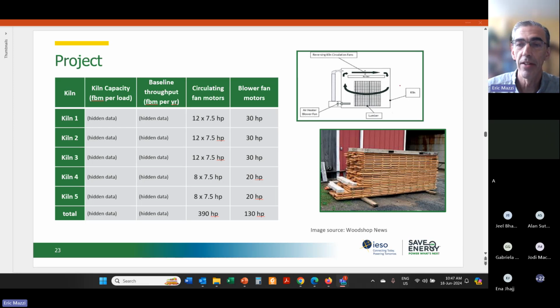So in short, it's a conventional lumber drying kiln, shown in the upper right here, and it's a batch process. The kiln is opened up and a skid of lumber is put in. There's a heating source in there burning natural gas to provide heat. There are circulation fans and it is vented to remove the moisture. As the lumber heats, moisture evaporates, from a starting moisture content down to a final moisture content. The measure of quality in this kind of process is percent moisture, once it gets down to the targeted moisture based on how it's measured. They also look for percent defects. Those are the key metrics involved.